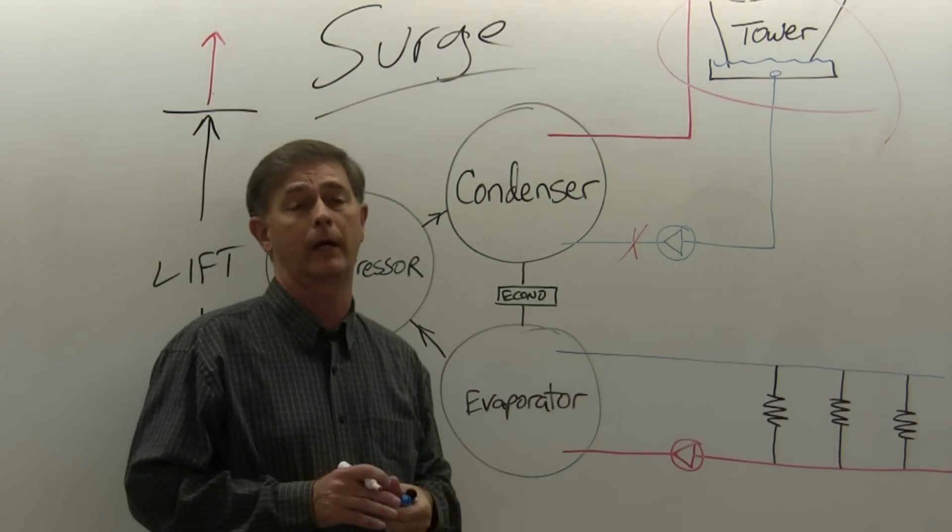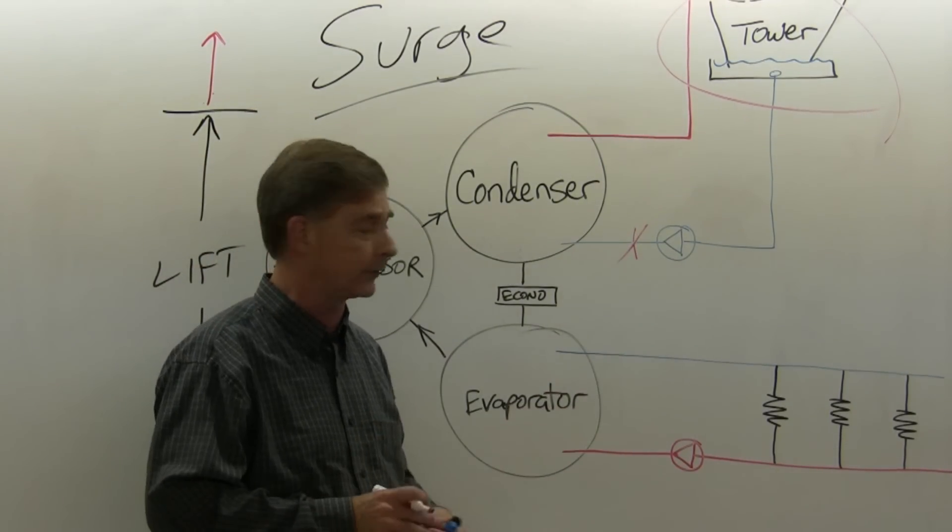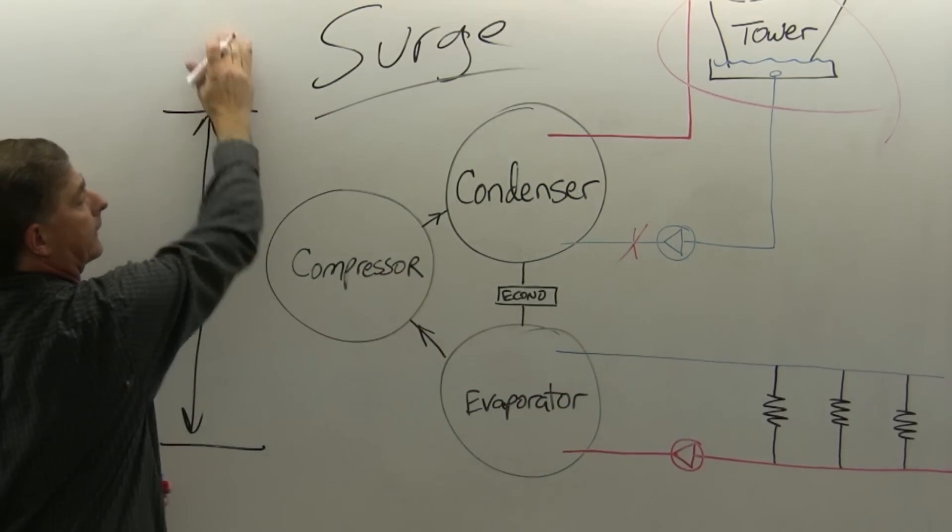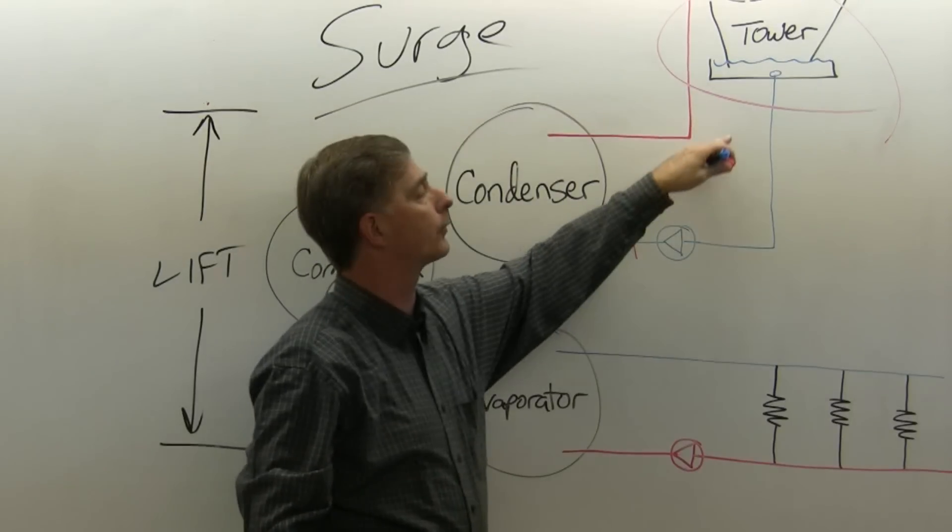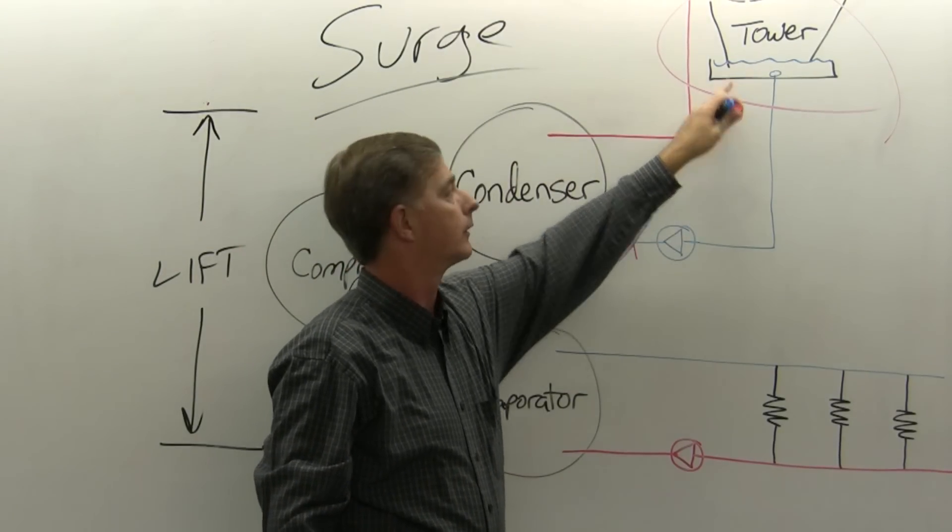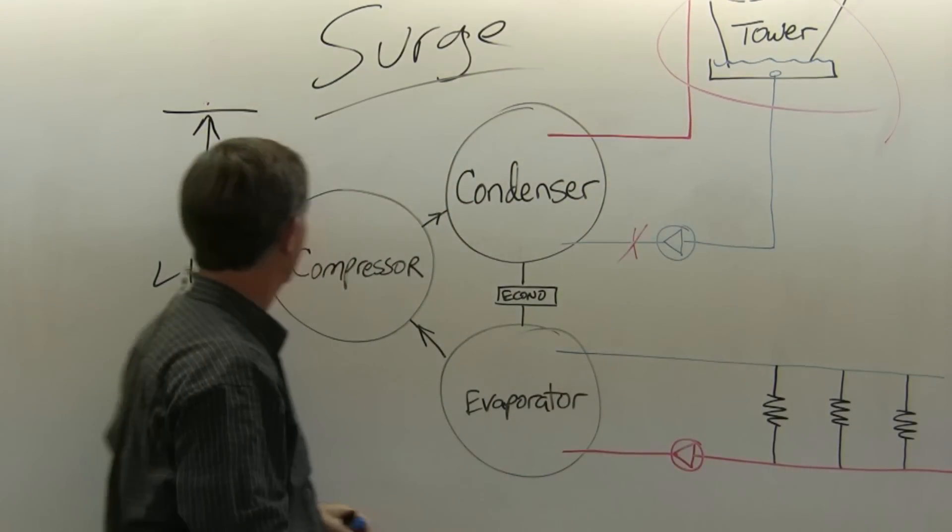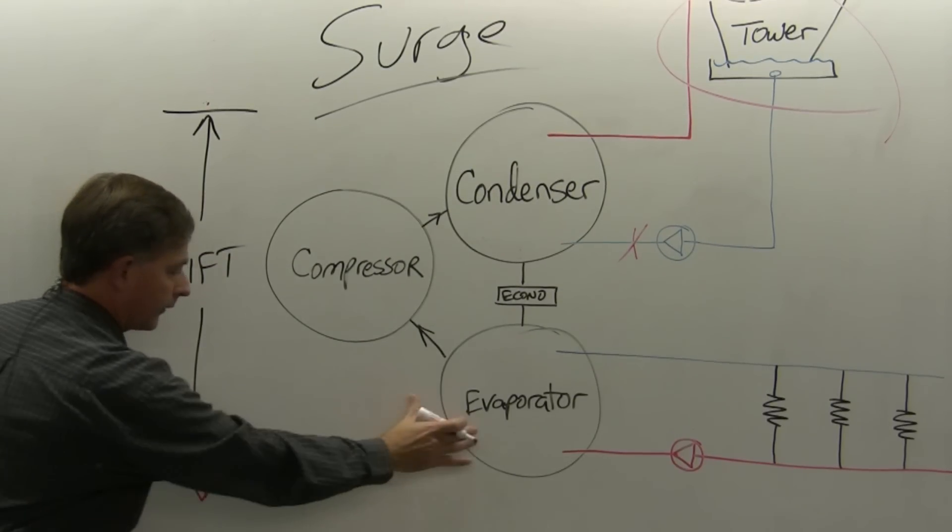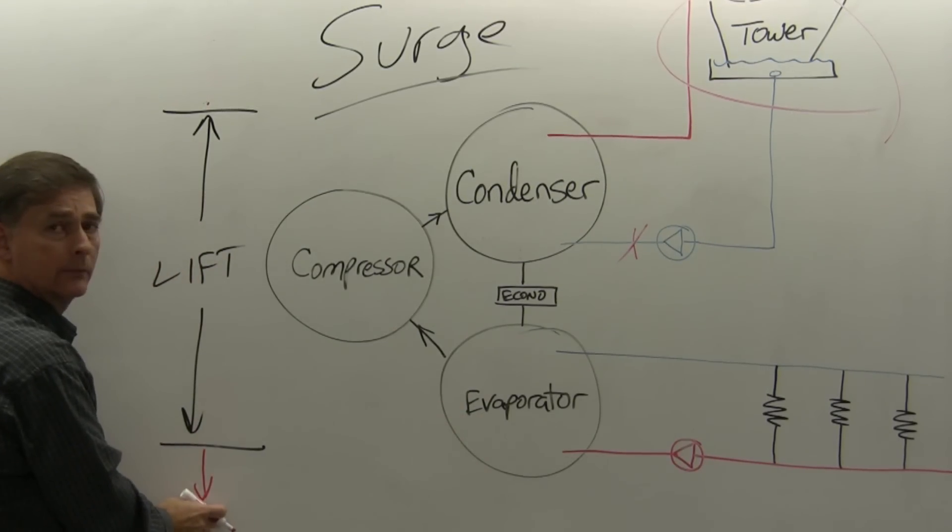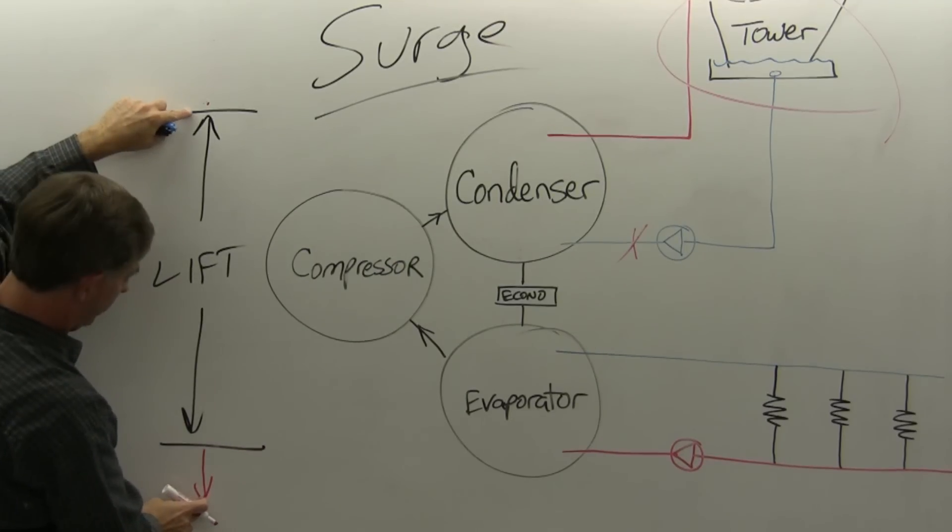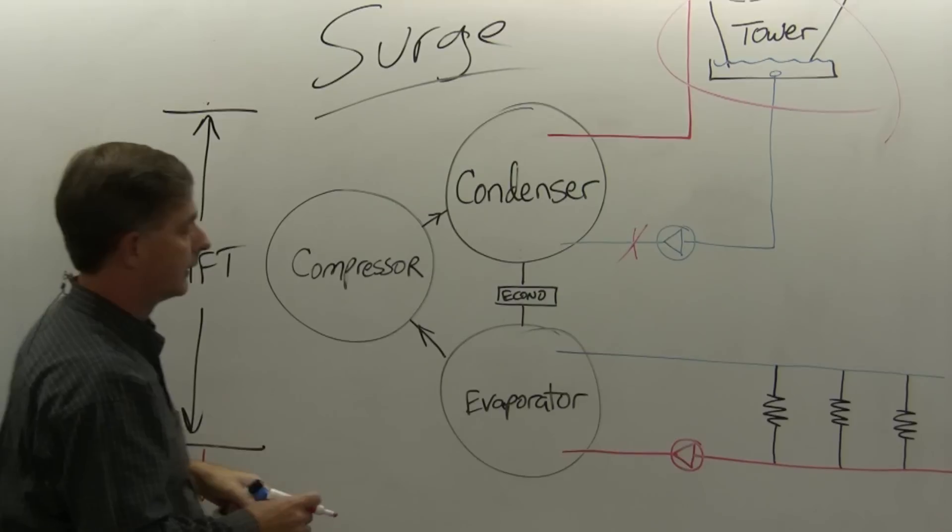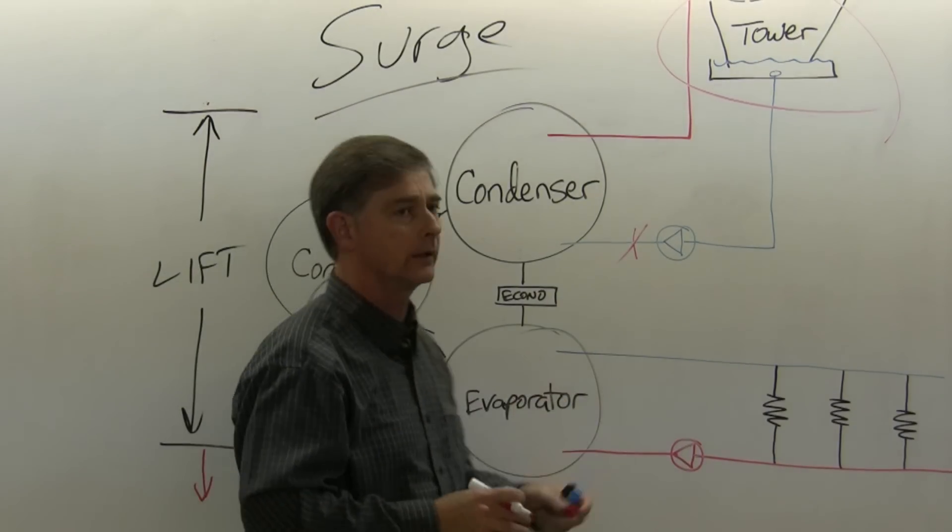You can also have surge on the low side of the machine. If we look down here, just like this line can go up for a number of different reasons related to this part of the system, we can also have our pressure in the evaporator drop, and that will also increase your lift and lead to surge. It's a little less common, but it does happen.